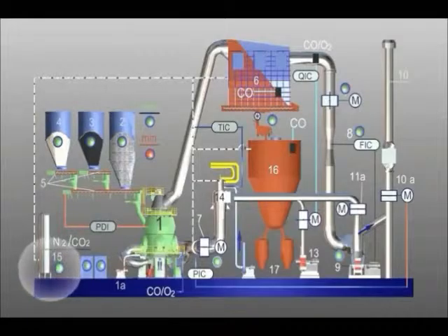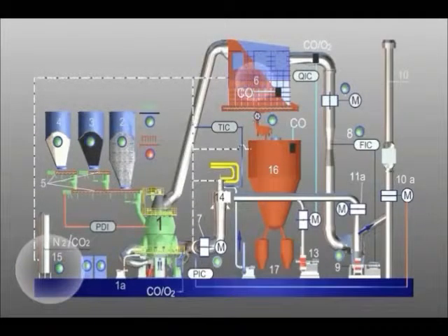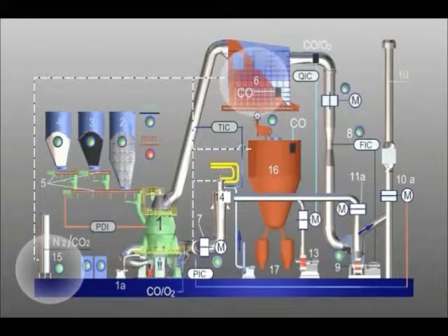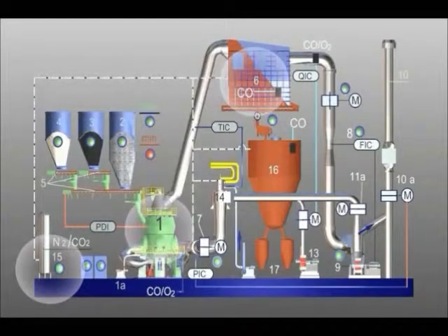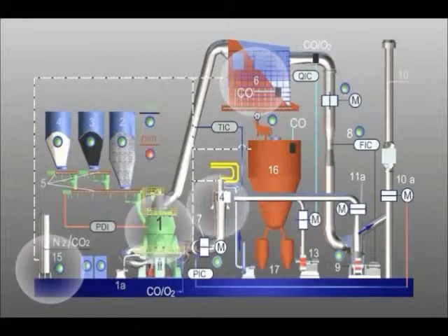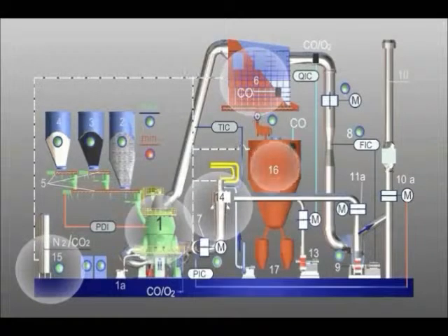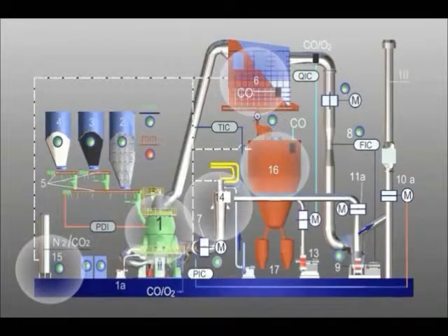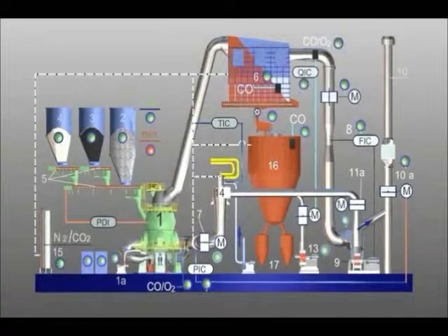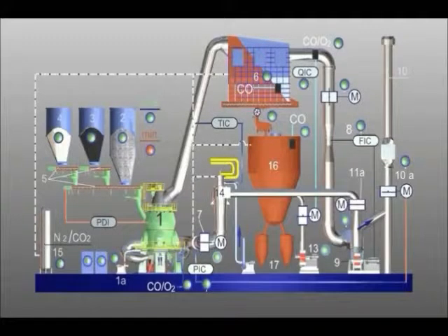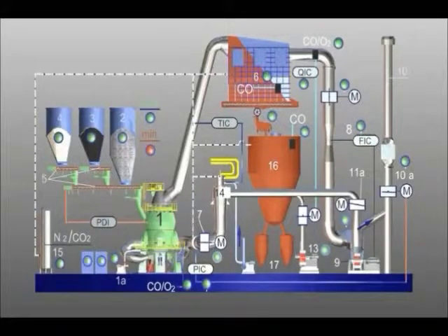Inert gas is applied to the following units: position six filter, position one mill, position 14 hot gas generator, and position 16 dust hopper. The gas analysis equipment is activated in order to determine the carbon monoxide and oxygen content of the process gas.